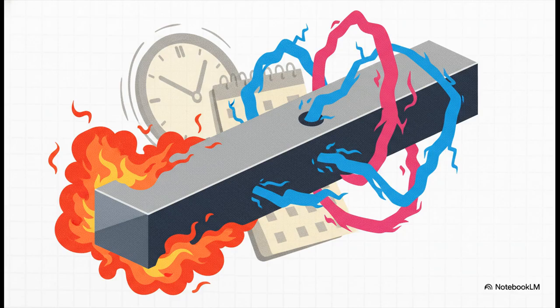A bus bar has to be unbelievably tough. Normally, it's dealing with extreme heat, but during a short circuit, the forces are insane. We're talking about currents that can suddenly spike to like 40,000 amps, creating massive electromagnetic forces that try to tear the part apart. And it has to withstand all of that for over 30 years.